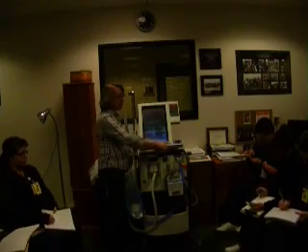So if you want to make sure that your alarms are on the highest volume. This is a 2-minute alarm silence right here. This is a reset. So if I silenced it and when I want to reset it, that's the next button over. Then over here on this side, you have 100% O2, which we will use for suctioning. You'll push that button, your patient will get 100% O2 for 2 minutes. Of course, we can't do that right now because we have no oxygen.